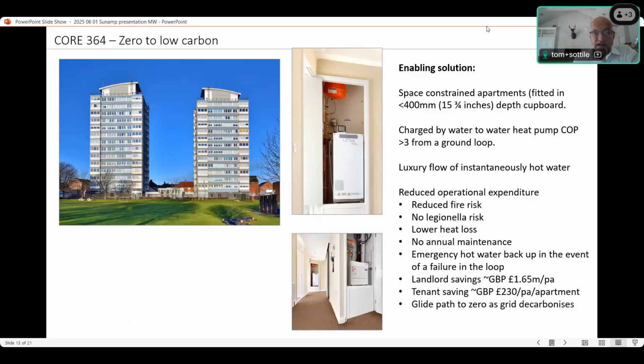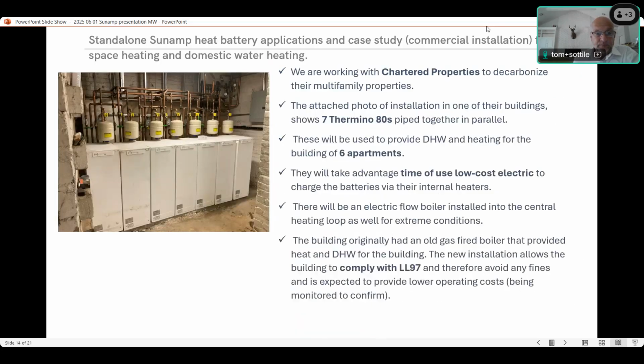I'm just going to run through some quick examples to demonstrate how the thermal batteries are applied. This is something we've replicated in the UK many times. It's what we call a tower block, a multifamily apartment building, where traditionally they had condensing modulating boilers in each apartment. Those were removed and a geothermal loop was put in, brought up through the building, where we use small water to water heat pumps to pull the energy out and store it in our thermal batteries. The combination of the two allows us to meet peak demand with a reduced size heat pump that we can operate on off-peak hours.